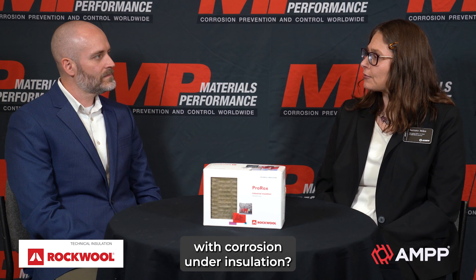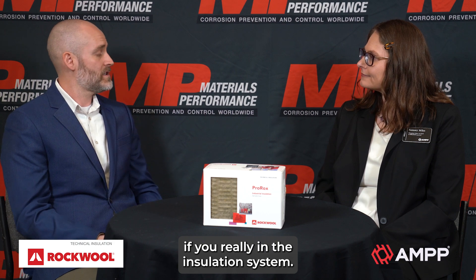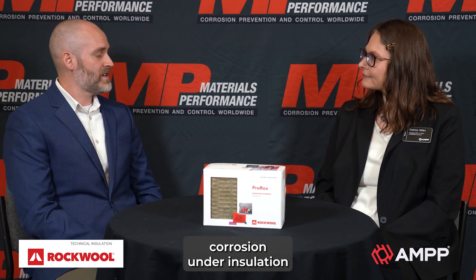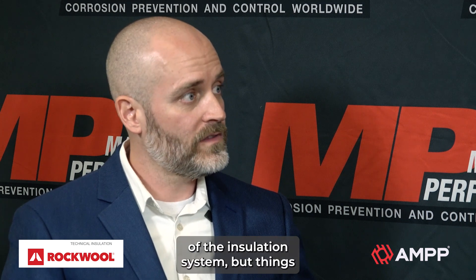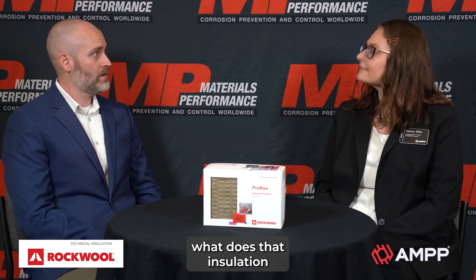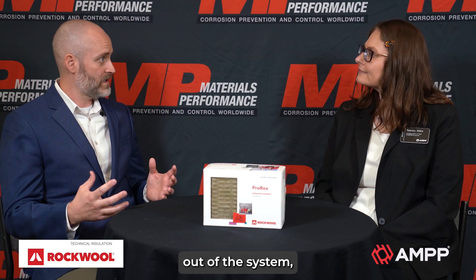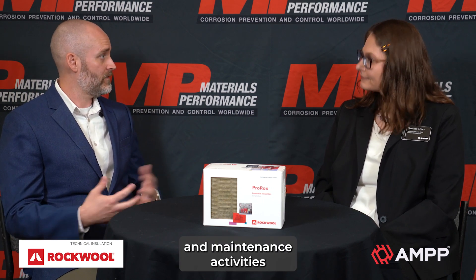Can you tell me what some of the challenges are with corrosion under insulation? In an insulation system, it's all about corrosion — insulation is about water being trapped under the insulation and being on metal. The real key is keeping water out of the system. There are various challenges with that, not just with the components themselves of the insulation system, but things where it becomes important to look at the early design: what is that insulation designed to do? Is it designed to keep water out of the system? But also things like inspection and maintenance — you don't know if you have water a lot of times in the insulation system. Are they doing the proper routine maintenance activities to determine if there is water, and then preventive things if there is?